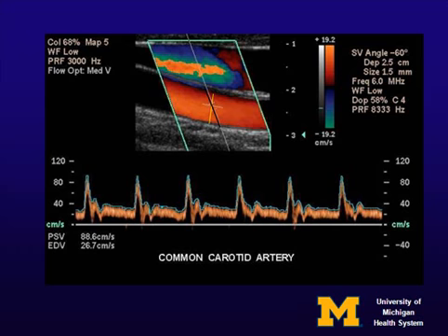The other thing is that the measurement is one-dimensional. As you can see, we are sampling along a line. That implies that the flow profile is cylindrically symmetric. And since the diameter that we're measuring is fixed, this doesn't compensate for any of the pulsatility in the blood vessel. All of these things are approximations which are almost invariably wrong, and because of that, very few people use volume flow as a standard portion of their imaging modality.